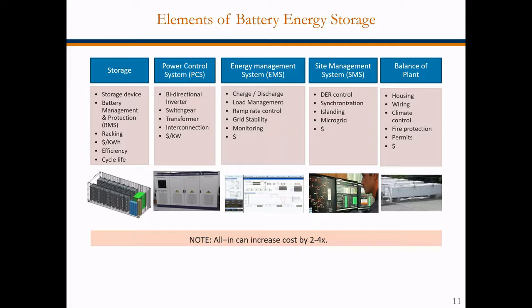That talks to the power control system, which consists of the bidirectional inverter, switchgear, transformers, and all the interconnection. That power control system talks to the energy management system. They're all interacting together, and the energy management system controls the charge and discharge. It's looking at the grid, getting feedback, and telling the power control system and the battery management system what they need.